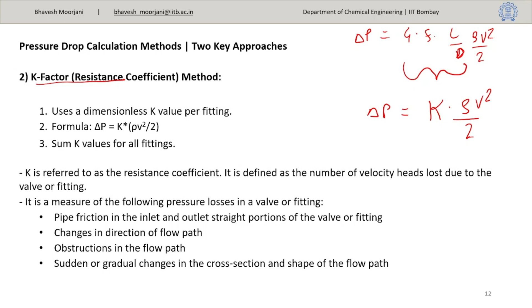So K is referred to as the resistance coefficient. It defines the number of velocity heads. Rho V square by 2 is the velocity head. Okay, so K times the velocity head will be your pressure drop in a system. Okay, and generally, from where do we get this K value?